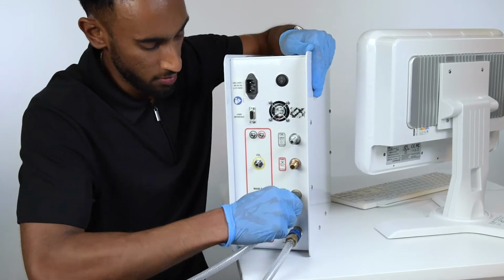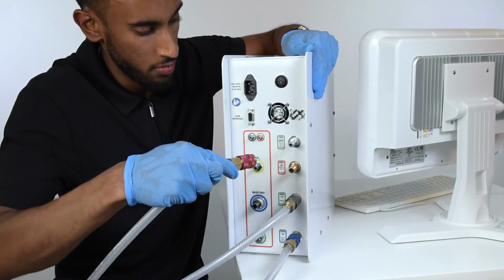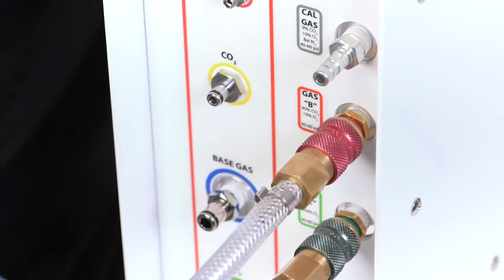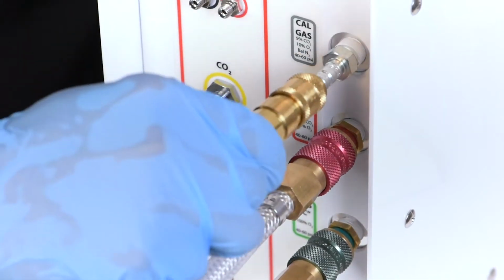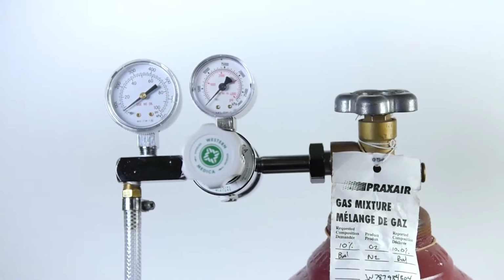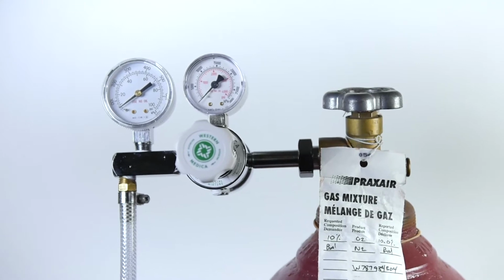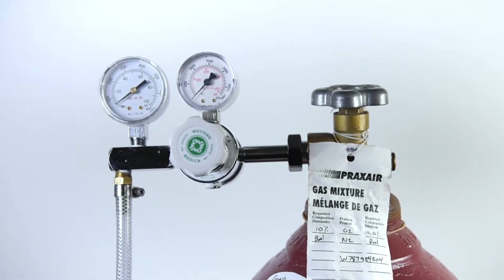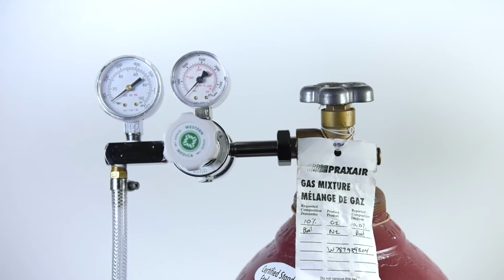Assuming your regulators are attached to their respective compressed gases, attach the 4 gas input hoses to their respective connectors on the back of the control room unit. The connectors are color and shape dependent so that they cannot be incorrectly connected. It is important that while connecting your gas inputs, the compressed gas cylinders are closed so that there is no pressure in the hoses. This will make it much easier to make connections between the two.